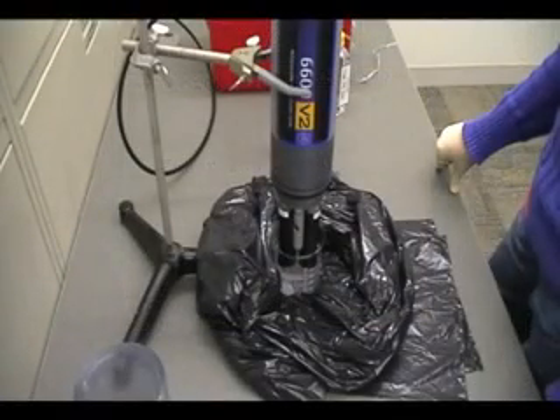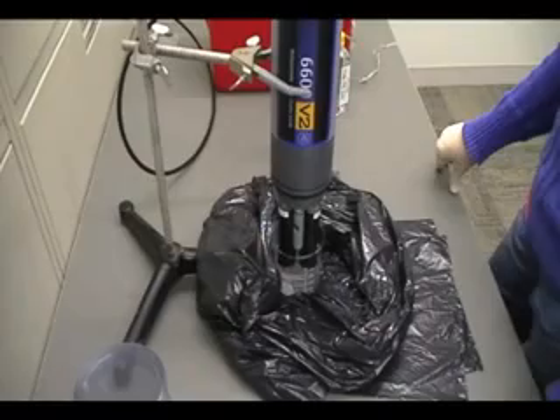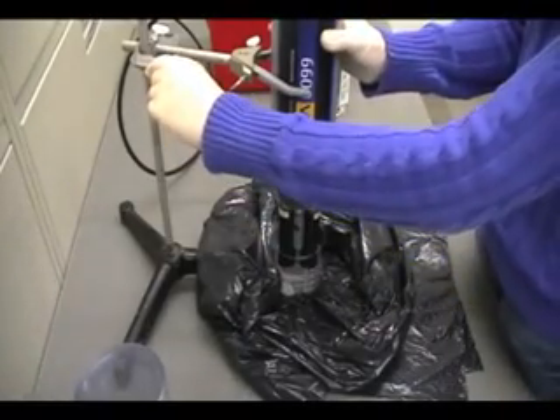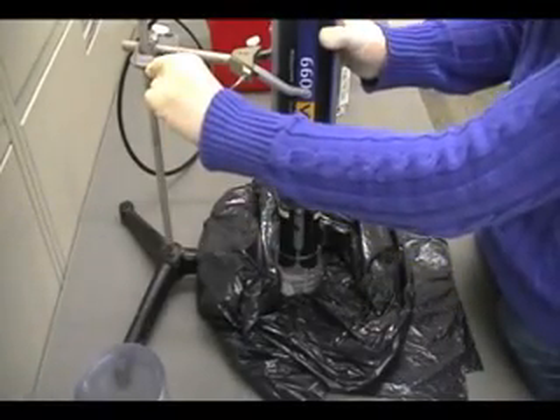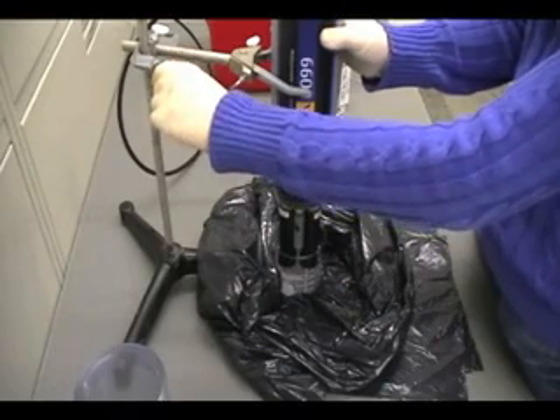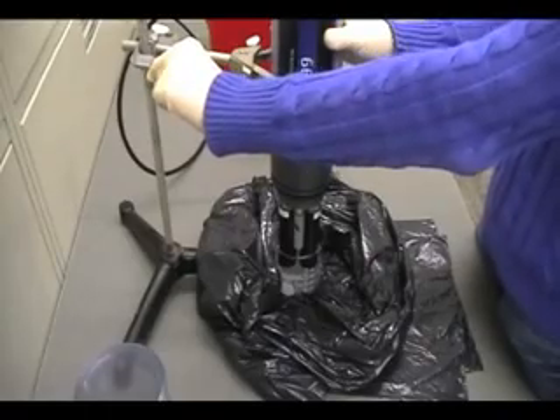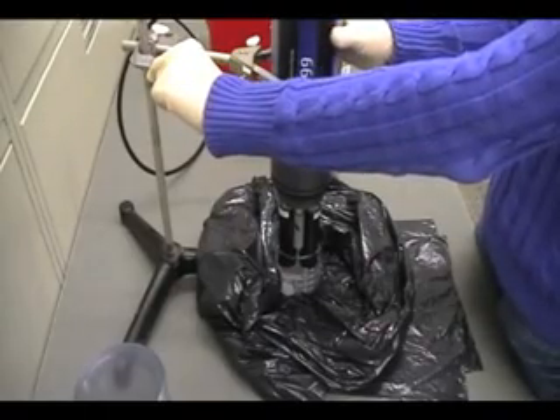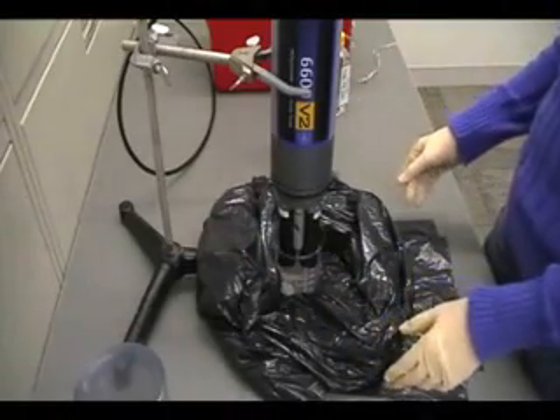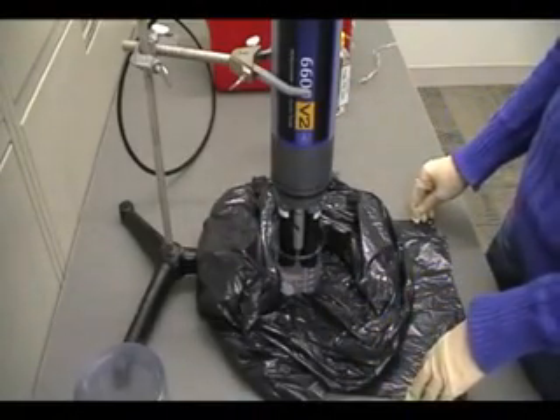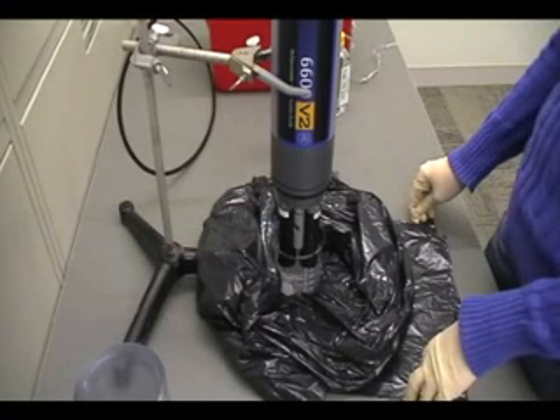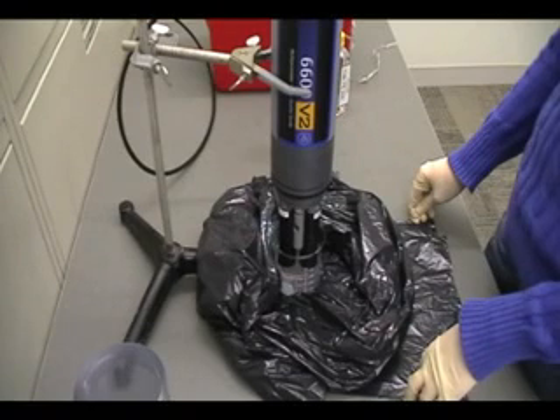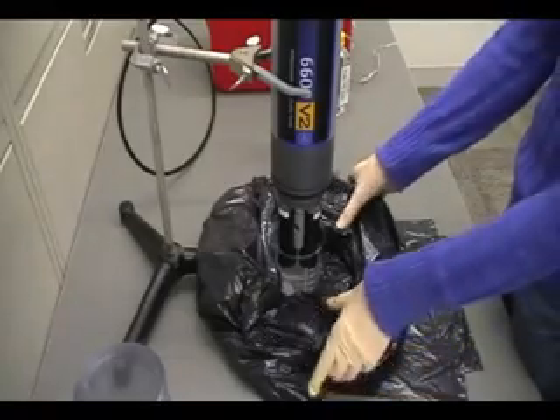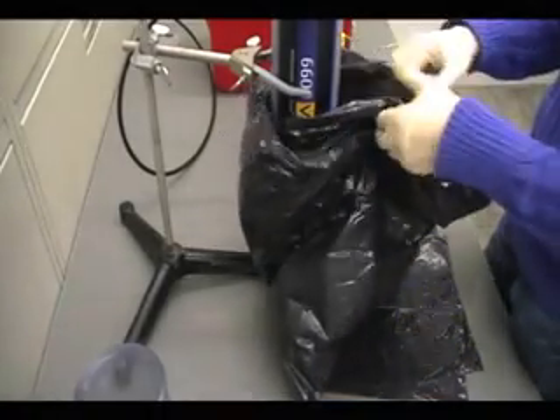Step 13. If the 0 NTU standard is in a jar with a wide enough mouth, lower the sensors into it so that only a few millimeters of the turbidity sensor are submerged. Note, this jar should not be plastic. It should be clear or dark glass, and it must be placed on something black. If the 0 NTU is not in a usable jar, pour some of it very slowly, avoiding bubbles, into the calibration cup so that the end of the turbidity sensor is submerged. Step 14. Reduce lighting in the room and wrap a black bag around the calibration cup or jar.